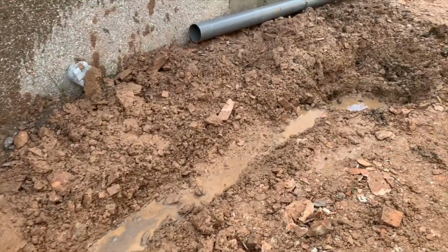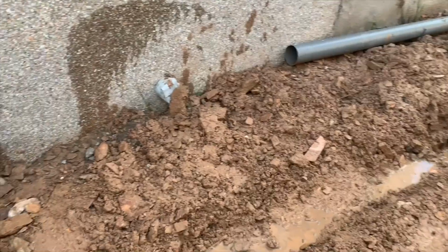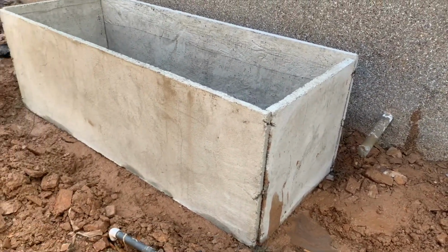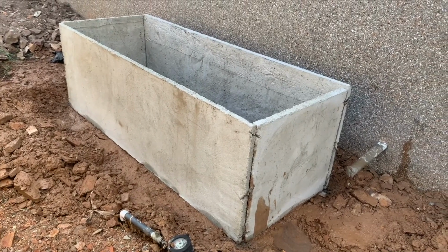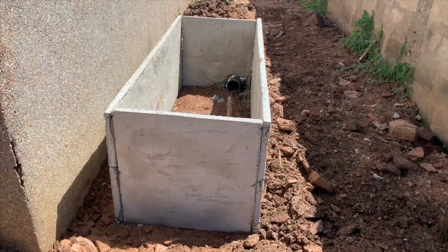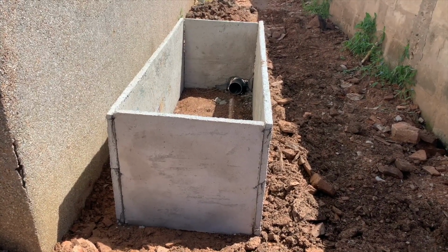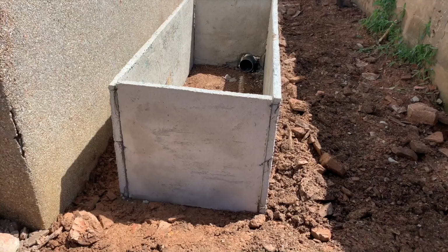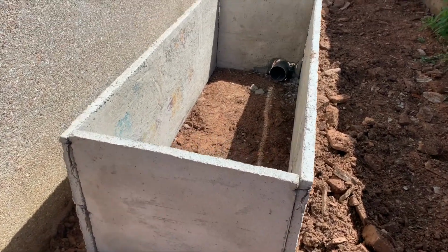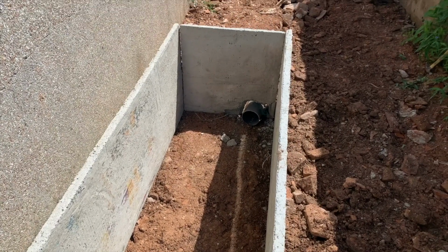So when you're going to replace a septic tank with a Biodigester, one, look out for how high the water table is; two, know the level of the pipes going into the tank; and three, look at the seats in the house, whether they are P-trap or there's enough room for the seats or the pipes coming into the digester to be elevated, because you don't want your digester to face the same problem the septic tank is facing.